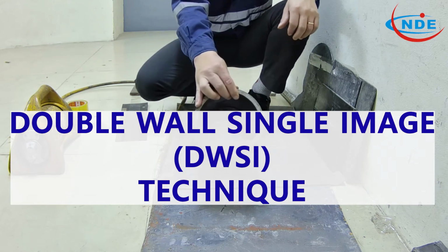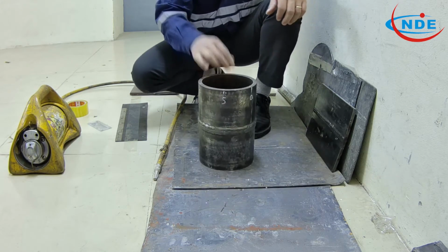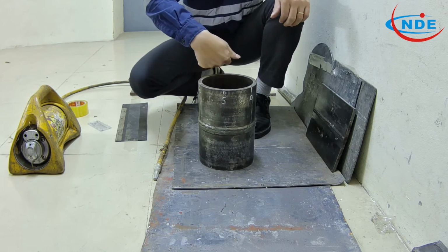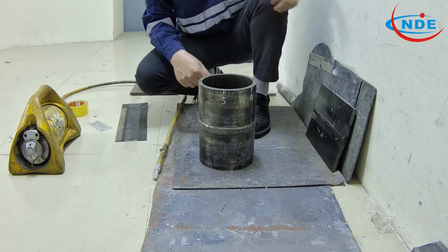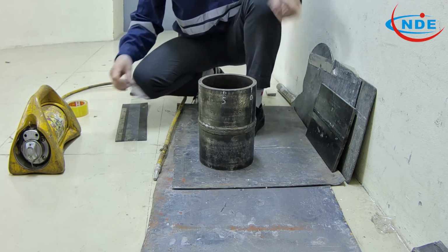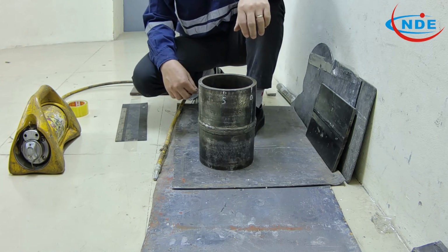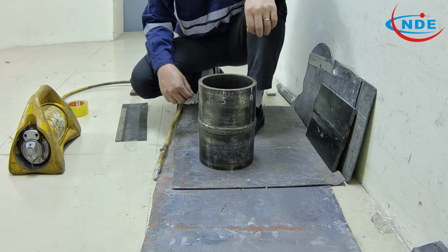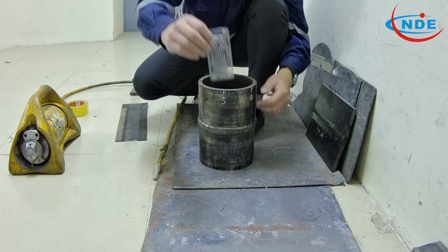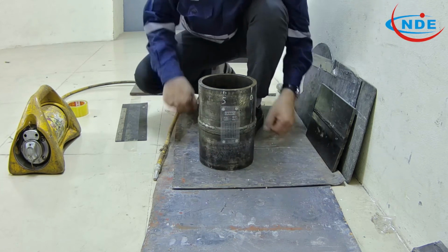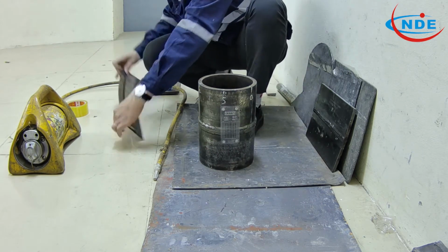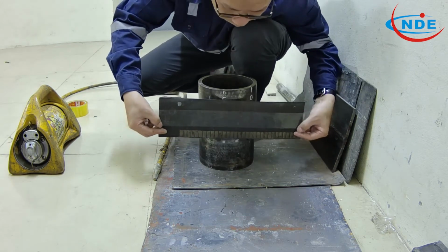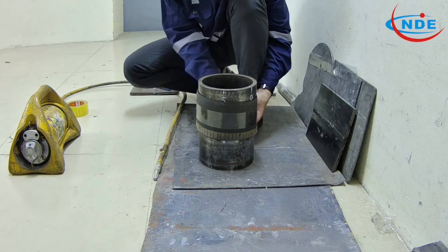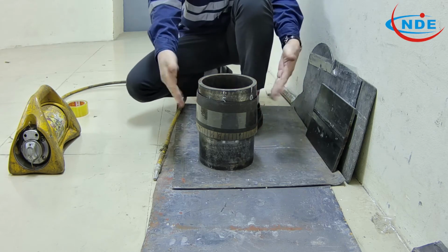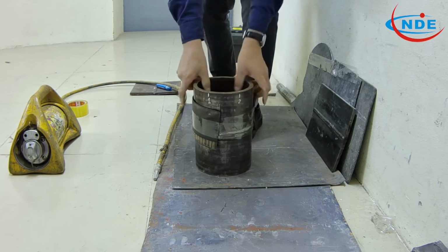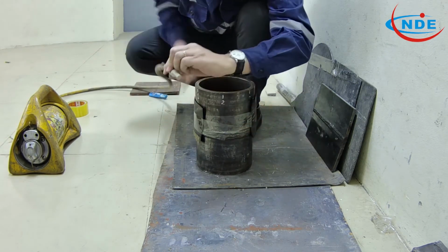For smaller pipe, the technique of double wall, single image will be used. The arrangement will be the IQI, the film, and the radiation source may be close to the pipe.